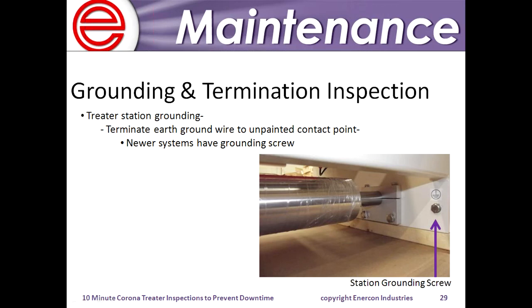You also want to make sure that there is an earth ground wire terminated to the frame of the station. In our newer systems, from the last few years, we actually have a specified point for earth ground termination. But basically, it's as simple as removing the paint at a location on the frame and terminating an earth ground wire to that. That way, you're not relying on the earth ground being terminated through bolts and threads and stuff like that.